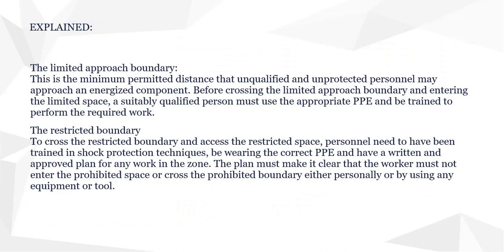The limited approach boundary is the minimum permitted distance that unqualified and unprotected personnel may approach an energized component. Before crossing the limited approach boundary and entering the limited space, a suitably qualified person must use the appropriate PPE and be trained to perform the required work.